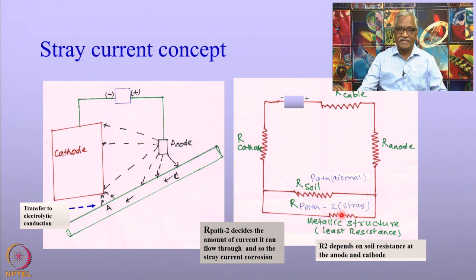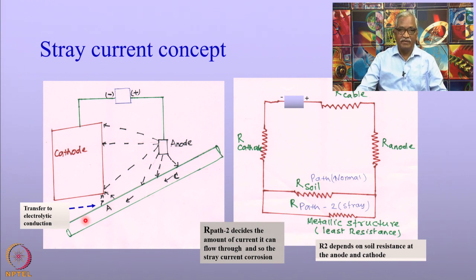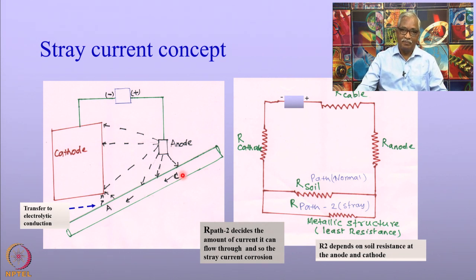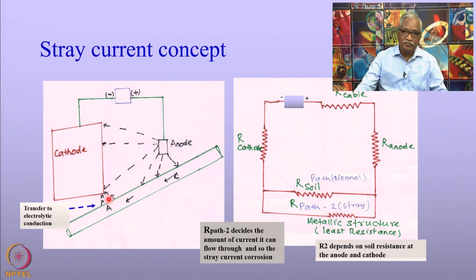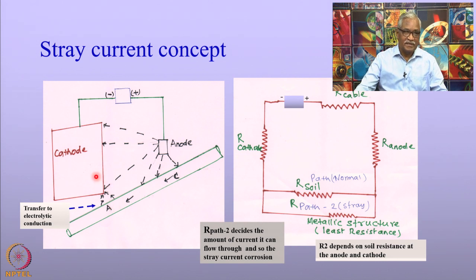To summarize: stray current corrosion occurs whenever a foreign pipeline or foreign structure lies in the vicinity of an already cathodically protected structure. A part of the current from the anode enters the foreign structure — the entry point becomes a cathode, and where the current leaves back to the circuit that becomes an anode. The location where it becomes an anode suffers severe corrosion. The extent of corrosion depends on the resistance offered by the soil between the anode, the foreign pipeline, and the buried structures.